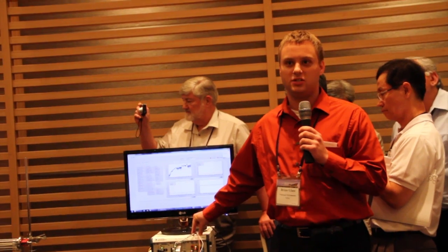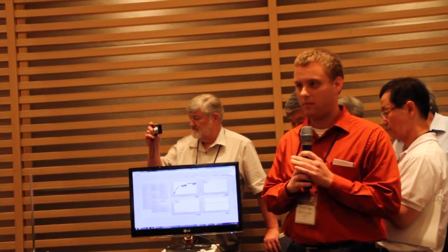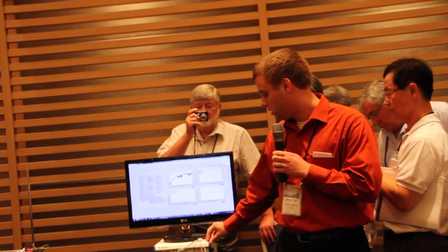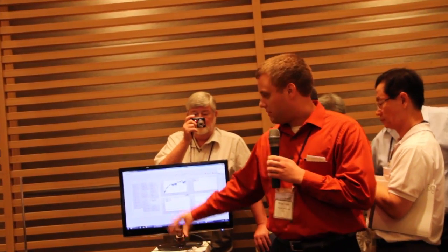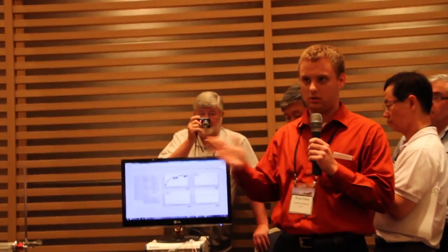And we have 2 digital multimeters, 7.5-digit multimeters, in here. One is performing a current measurement and one is performing a voltage measurement. So from there we can calculate the total power input, I times V, and also the resistance of each wire with the division. To make measurements on each wire, there's the constantan wire running through the system, and then a reference wire, which is the nickel chrome wire, and we want to do measurements on each of those close to each other.